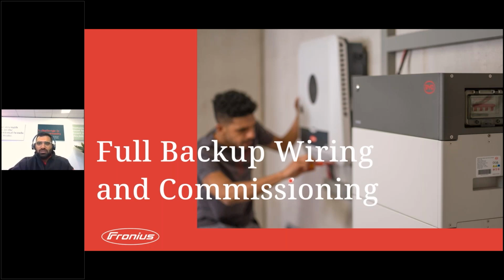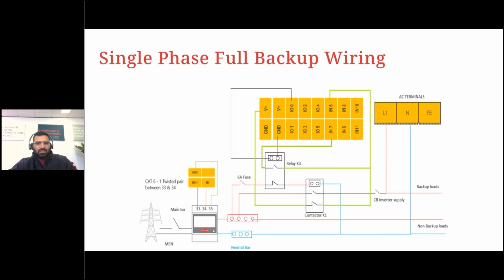All right, moving on to the main topic of this webinar. How do we do full backup wiring and how do we commission it? First thing you would notice here is that the backup is actually outside the inverter. In my opinion, it's a good thing that if the inverter fails, the customer still has a grid connection available and he's not sitting in the dark. Now, for us to run the inverter in backup, we must disconnect the backup circuit from the grid. So we need a contactor to disconnect the backup loads from the grid connection. This is to avoid feeding power back into the grid in a blackout scenario, which could be fatal for people working on the power lines during an outage.